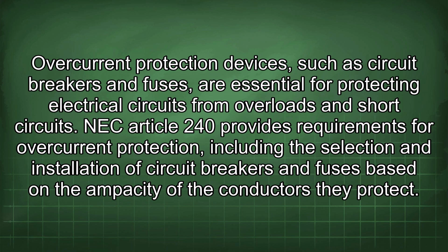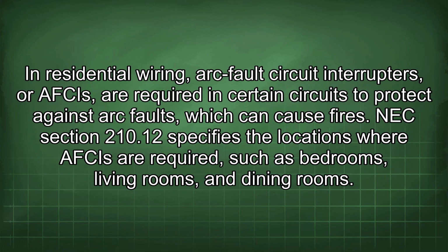Overcurrent protection devices, such as circuit breakers and fuses, are essential for protecting electrical circuits from overloads and short circuits. NEC Article 240 provides requirements for overcurrent protection, including the selection and installation of circuit breakers and fuses based on the ampacity of the conductors they protect. In residential wiring, arc fault circuit interrupters, or AFCIs, are required in certain circuits to protect against arc faults, which can cause fires. NEC Section 210.12 specifies the locations where AFCIs are required, such as bedrooms, living rooms, and dining rooms.